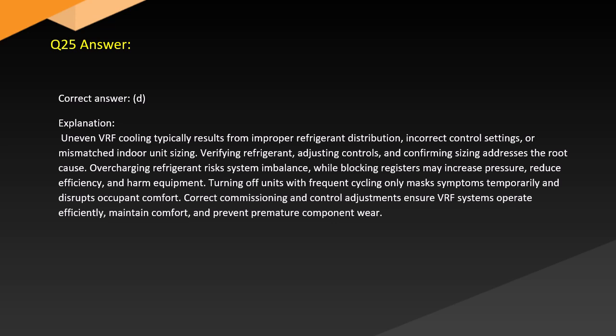Answer. Correct answer. D. Explanation. Uneven VRF cooling typically results from improper refrigerant distribution, incorrect control settings, or mismatched indoor unit sizing. Verifying refrigerant, adjusting controls, and confirming sizing addresses the root cause. Overcharging refrigerant risks system imbalance, while blocking registers may increase pressure, reduce efficiency, and harm equipment. Turning off units with frequent cycling only masks symptoms temporarily and disrupts occupant comfort. Correct commissioning and control adjustments ensure VRF systems operate efficiently, maintain comfort, and prevent premature component wear.